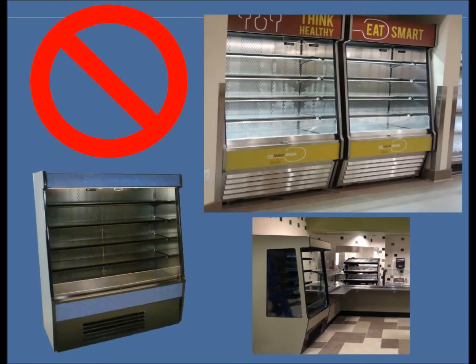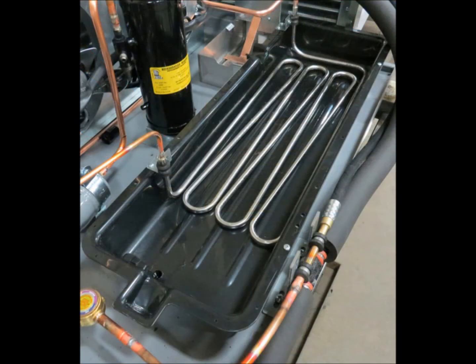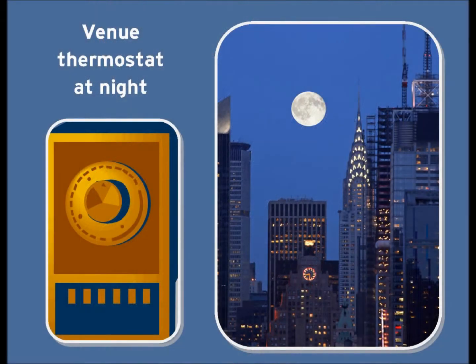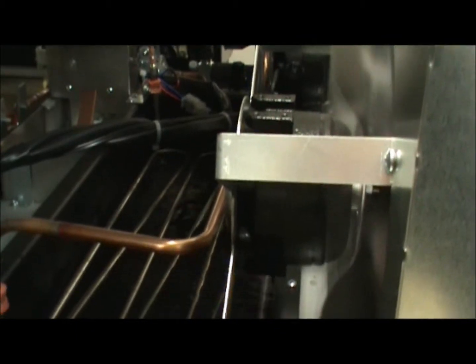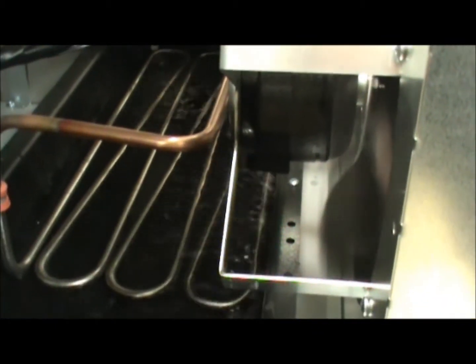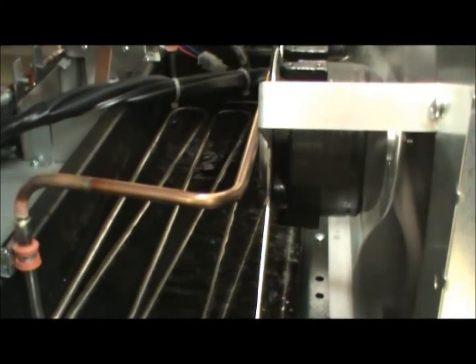Emptying product from the case overnight will cause the case to run harder and put more water into the evap pan, which could cause the pans to overflow. If you are adjusting your venue thermostat at night, this can also cause the case to run harder, creating more water for the hot gas loop to evaporate.